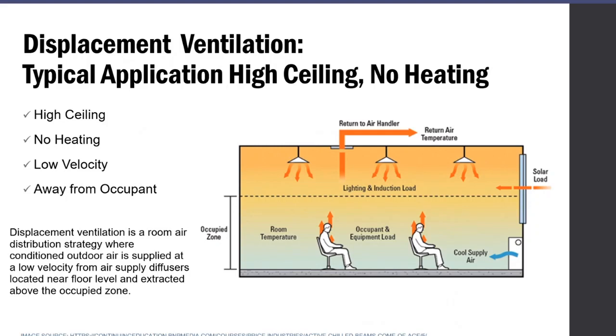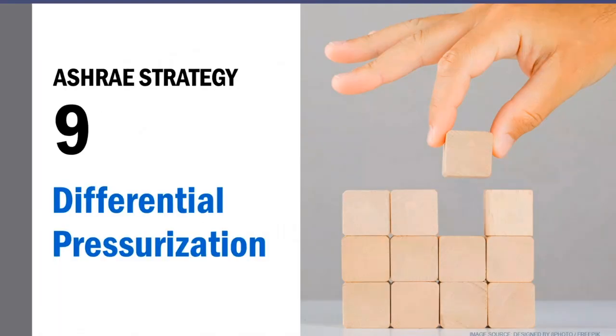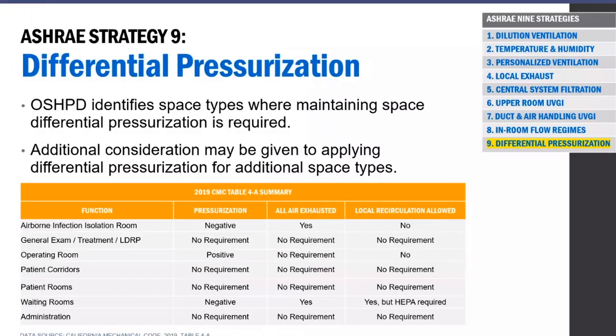Okay, codes are being changed as we speak—we'll see. The last item on this ASHRAE strategy is differential pressurization; basically, go back to OSHPD, the table speaks for itself. This is a summary of the 2019 CMC Table 4A, which requires special pressurization for different kinds of spaces: negative pressurization for airborne infection isolation rooms, positive pressurization for operating rooms to prevent contamination, and negative pressure for waiting rooms.